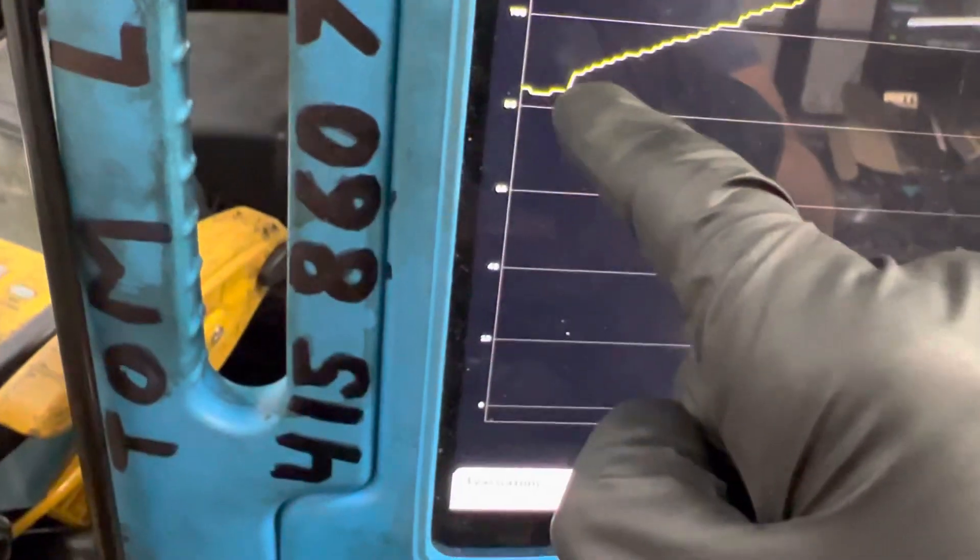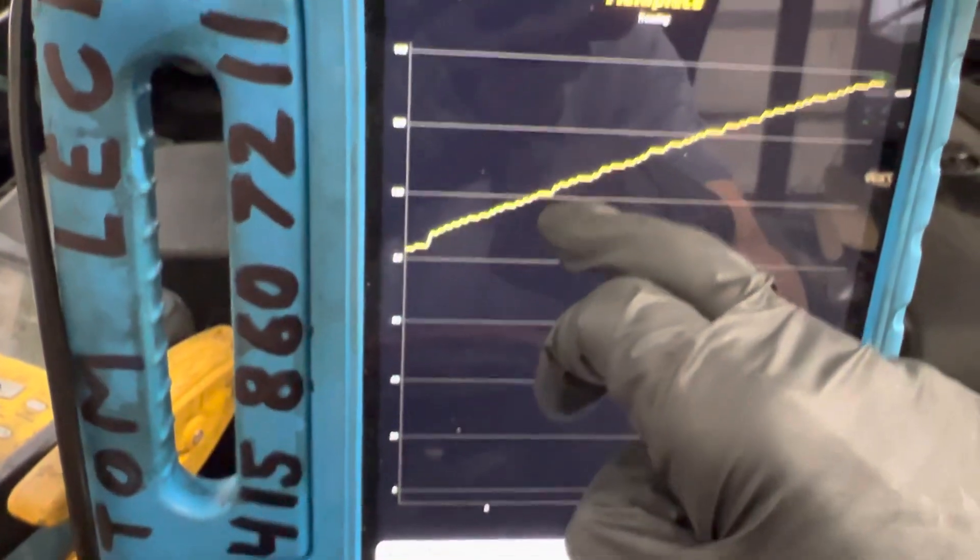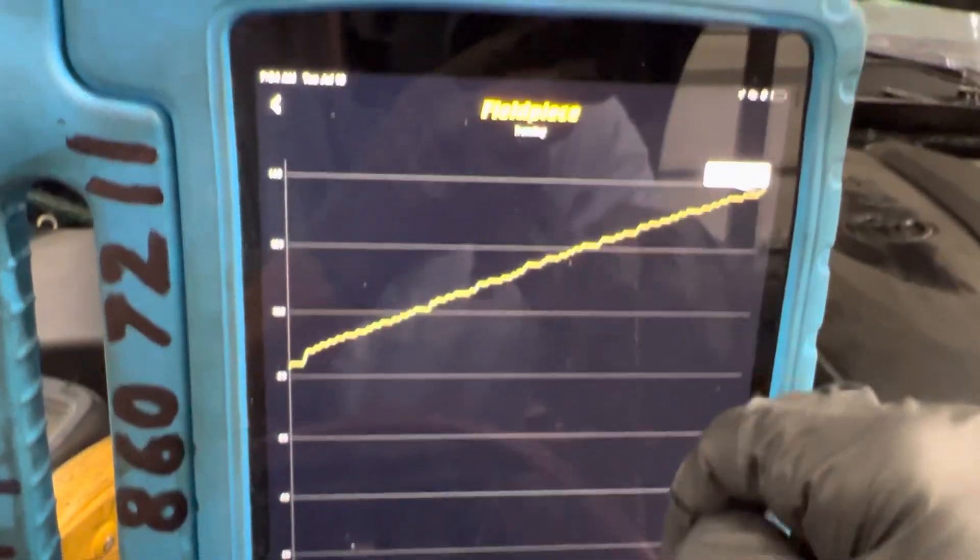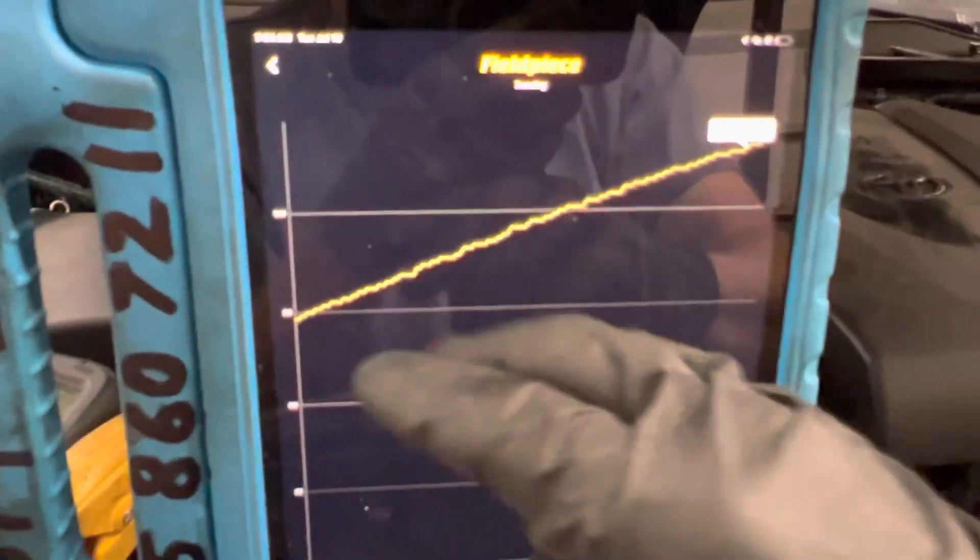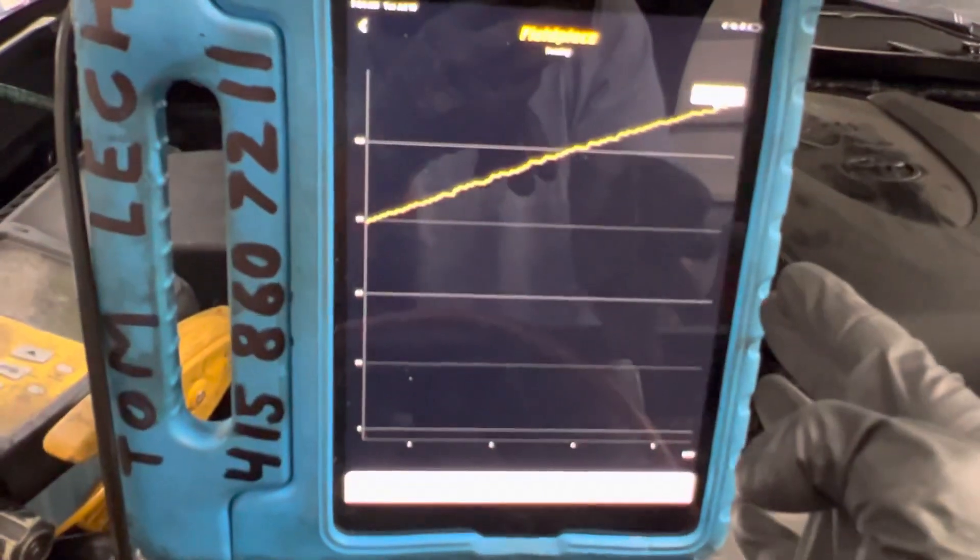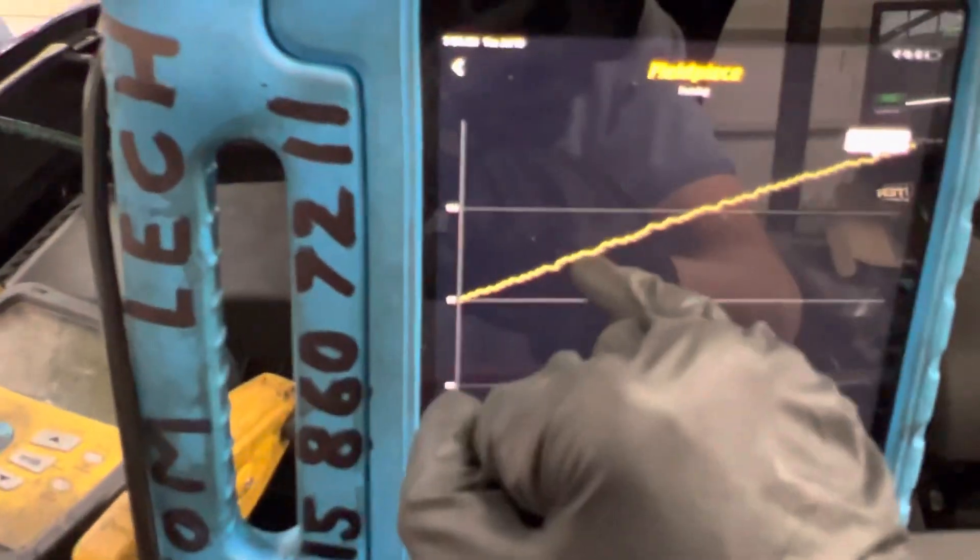Right here where you see the rise, that's where I turned off the vacuum source. There's this gradual increase and we're up to almost 140 microns now - 138 microns right there.